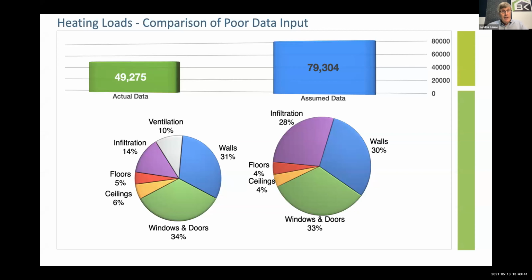Oh, and that is a good point. Knowing that you have a heat loss of 49,000 BTUs, what size furnace should you put in? Well, you got to put in something that gets you at least 49. And it's totally fine to oversize it by 10 to 15 to 20%. So that means a 60 is just nice. There's nothing wrong with a 60,000 BTUs. You're going to be just fine. No need to go to a 75 or an 80. 60 is going to be fine.